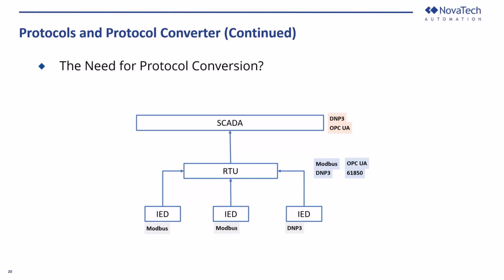So I've got a scenario. I've got three IEDs. Two of them talk Modbus, one of them talks DNP, and those are sending data to the RTU. An RTU can talk, hypothetically, Modbus, OPC UA, DNP3, and 61850. So now the RTU is able to get the data from Modbus and DNP, but the SCADA only talks DNP3 and OPC UA. So in this condition, the RTU has two ways. One is to get that data from the devices and either send it to SCADA via OPC UA or convert it to DNP. So this is just a small example of why we would need a protocol conversion, and the RTU can do that to ensure efficiency and reliability in the automation control systems.